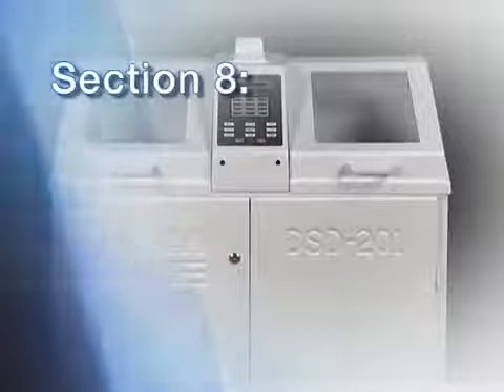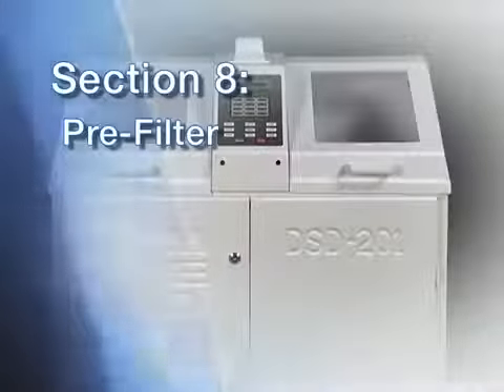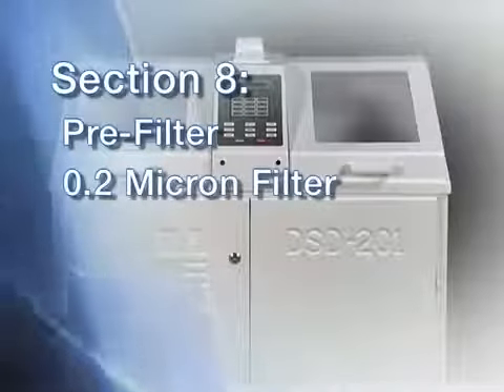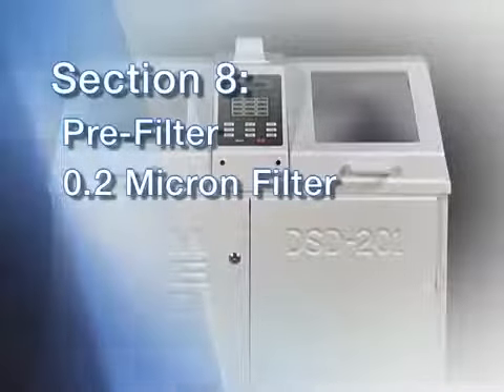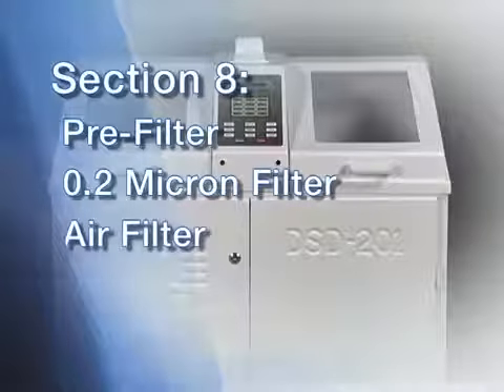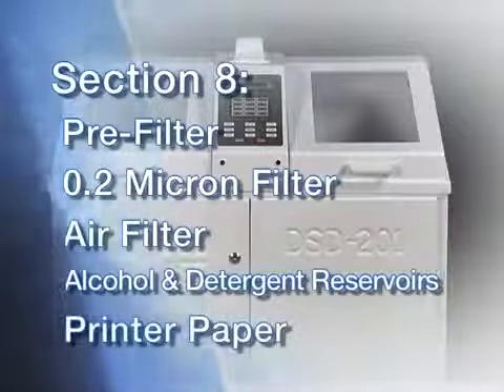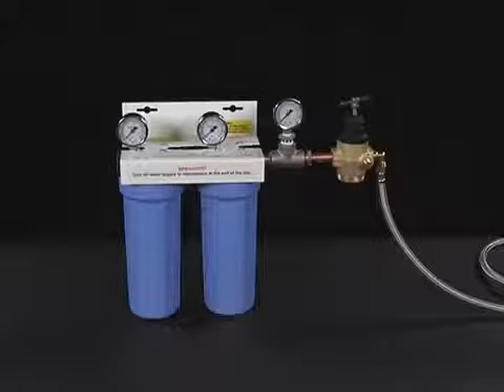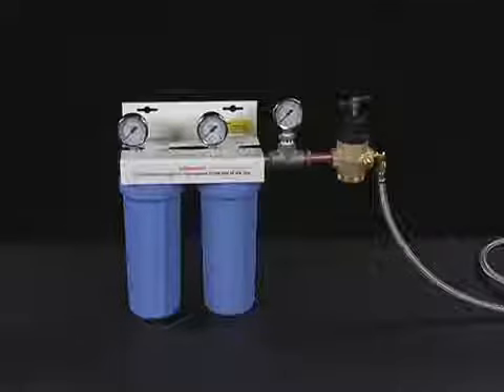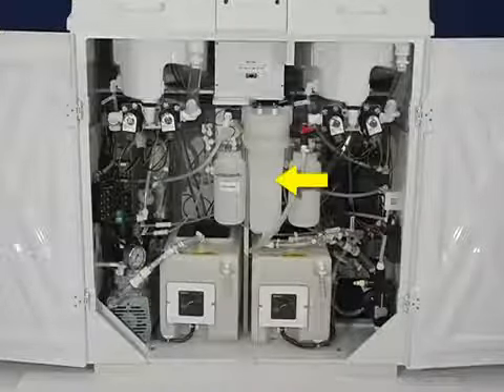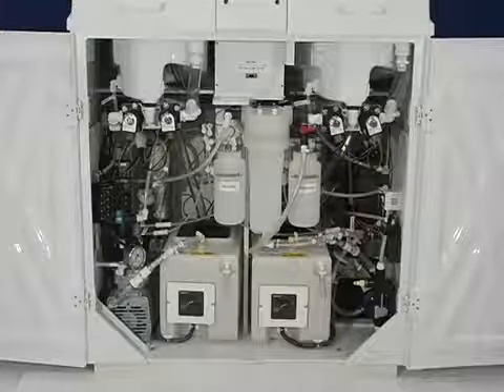In this section, we discuss water filter maintenance, including the external water pre-filters, the internal 0.2 micron filter, and sanitizing the water lines. Then we will discuss routine maintenance items such as the air filter, alcohol and detergent reservoirs, and the printer. Water quality can vary geographically, seasonally, and intermittently, depending on a variety of factors. The water pre-filtration system filters water in a step-down fashion. First through a 1 micron filter, then through a 0.45 micron filter to extend the life of the internal 0.2 micron bioretentive filter. Water quality and water volume affect the filter's useful life.